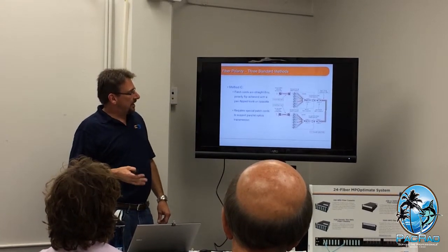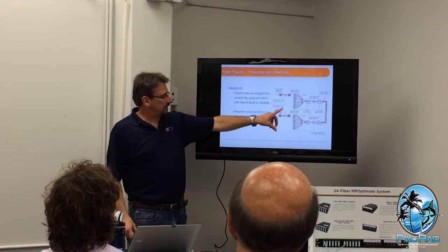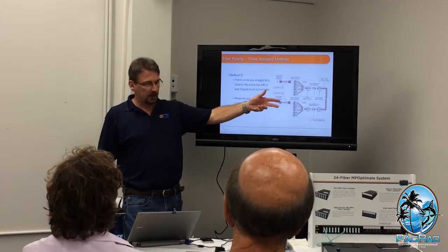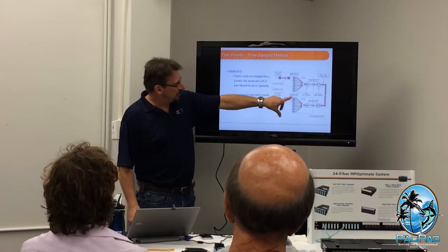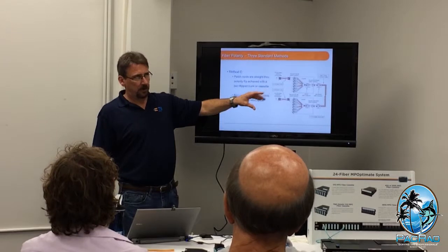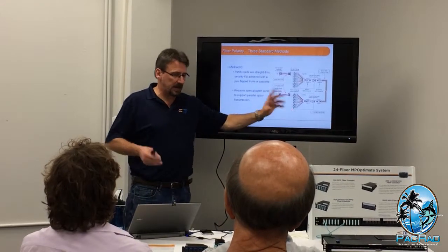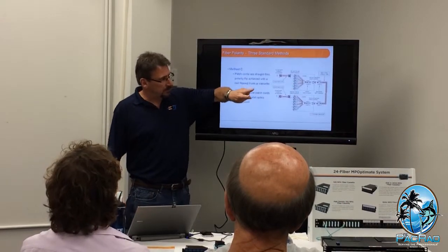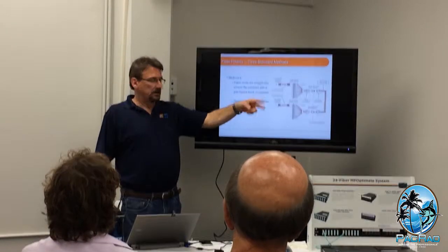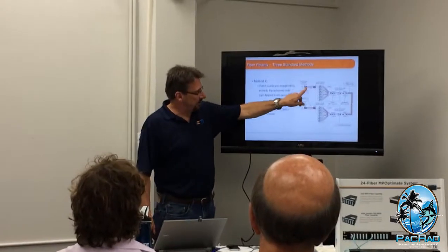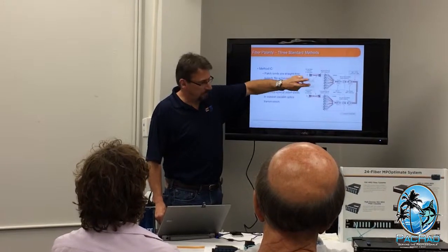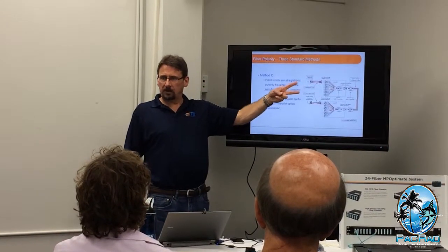Okay, the last method that was acknowledged for duplex fiber signaling was what was called pair flipped. Somewhere in the circuit, an odd number of components, whether it was one cassette, a cassette, a trunk and a cassette, whatever, had the pairs flipped. As long as it was an odd number, you knew you were going to go end to end and they were going to be rolled, just that single pair.